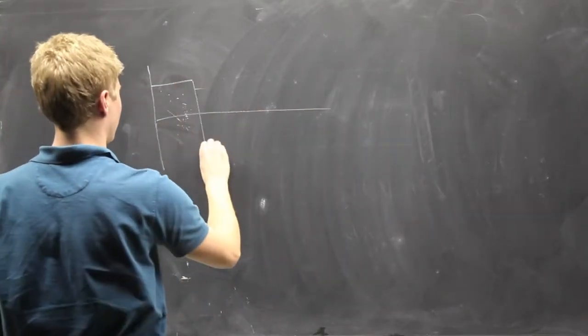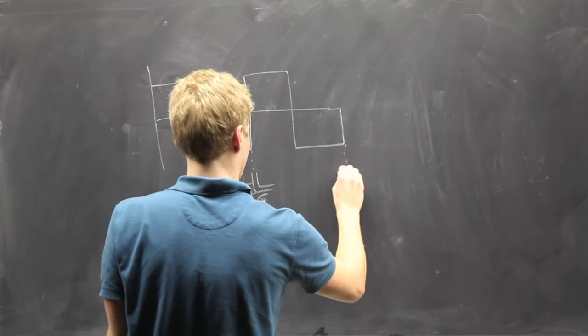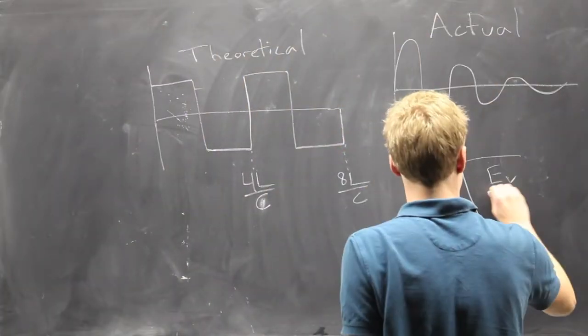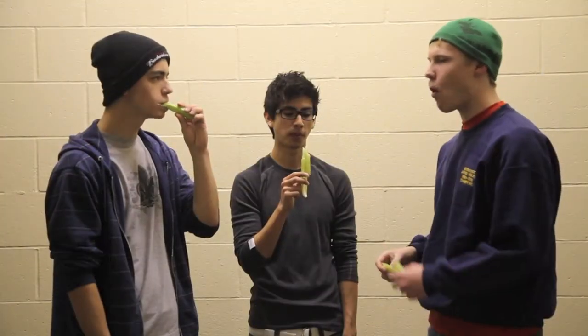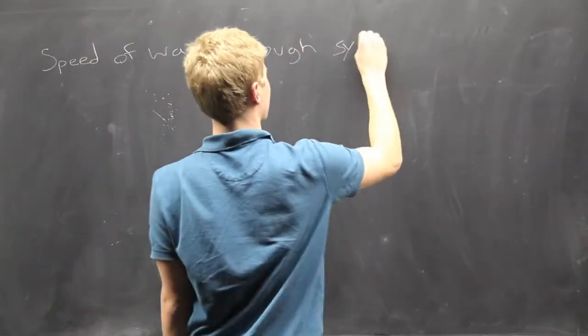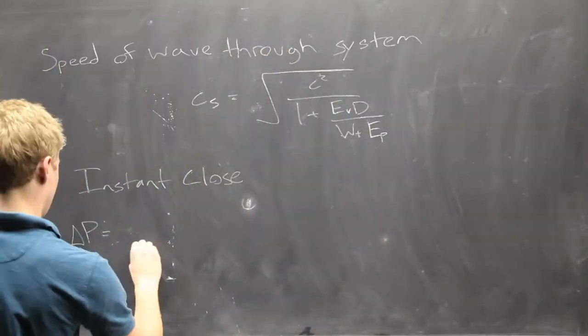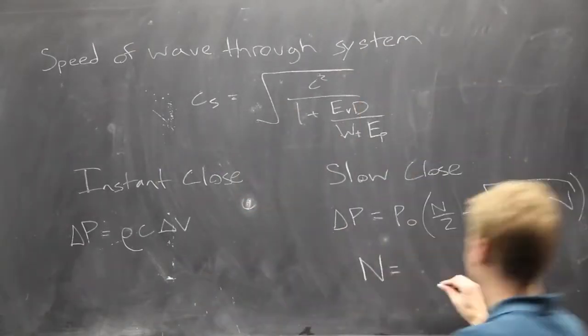The pressure at any point in the pipe at any point in time can be given by a celerity wave, which has a period of 4 times the length of the pipe over the speed of sound in the pipe. This is not to be confused with other types of celery waves. The speed of the celerity wave depends on the speed that sound travels through the system, and the pressure in the pipe depends upon whether or not the valve is closed before the wave returns.